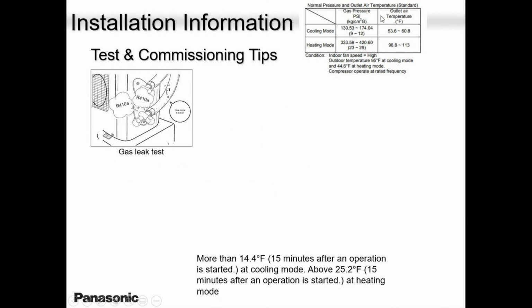Never join wires. Never. Some guy will tell me, Paul, you told me not to join. I joined. The unit is running fine. But guess what? After a couple of weeks, they'll be called back with an H11 code, a communication error. So please avoid these joints, guys. Or use a new wire. If you have to go back to the store, go and get it. Never join wires, regardless of power or control. Control wiring is worse.